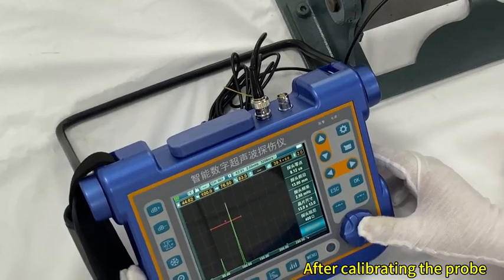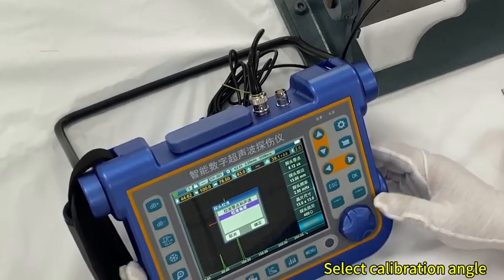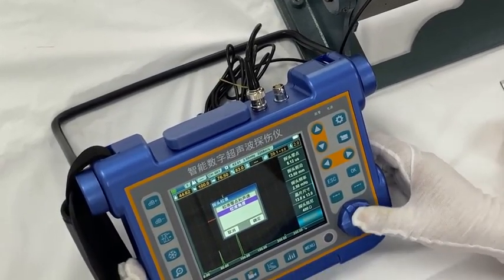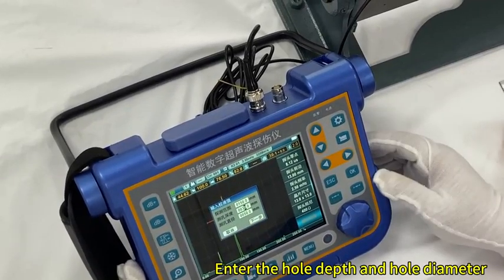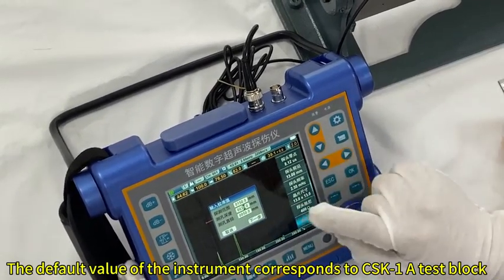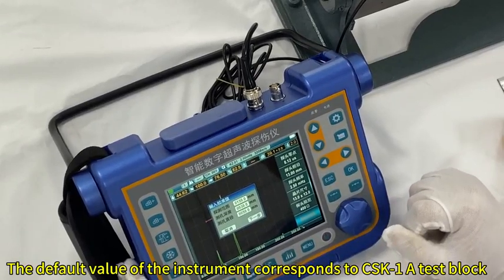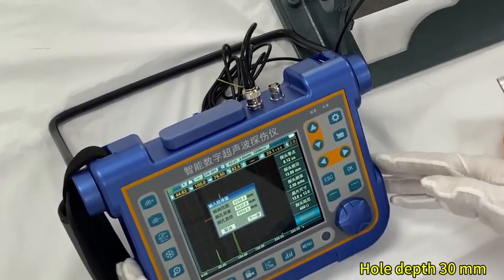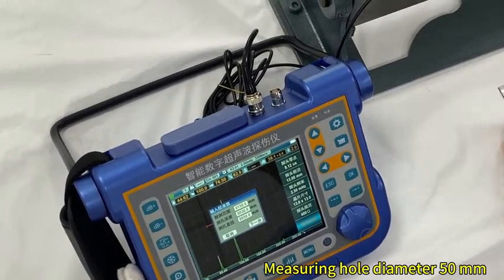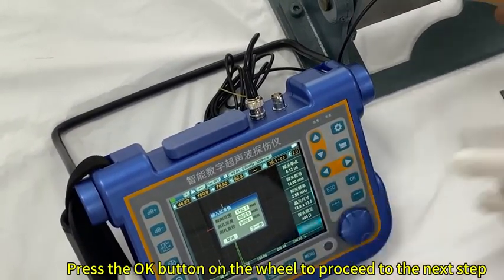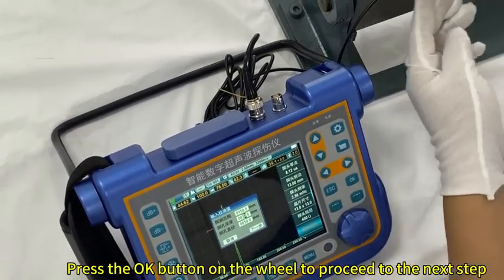After calibrating the probe, select calibration angle. Follow the on-screen prompts. Enter the hole depth and hole diameter. The default value of the instrument corresponds to the CSK-1A test block. Hole depth 30 mm. Measuring hole diameter 50 mm. Press the OK button on the wheel to proceed to the next step.